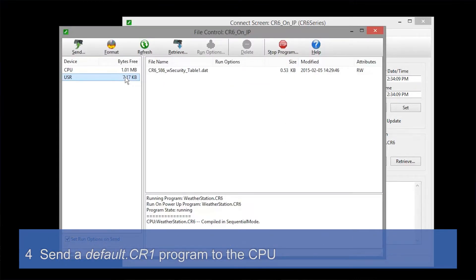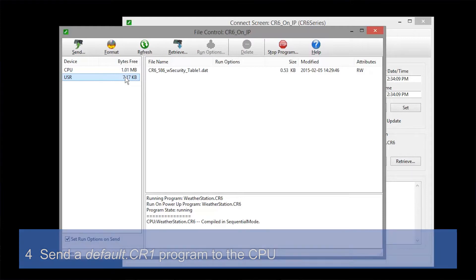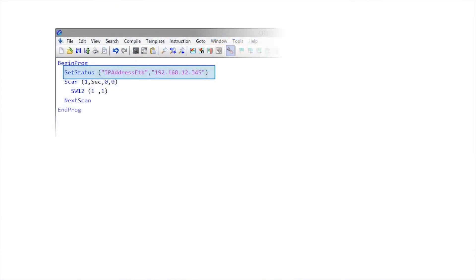Next, we'll send a special program called Default to the data logger. The Default program is one that you write in the CR Basic editor — it should be just a few lines to preserve critical data logger settings, such as those for communication. See your data logger's manual for more information on the Default program. Here I've used the SetStatus instruction to set the IP address. Another common instruction in a Default program is the SW12 instruction — here it is used to turn on a phone modem.